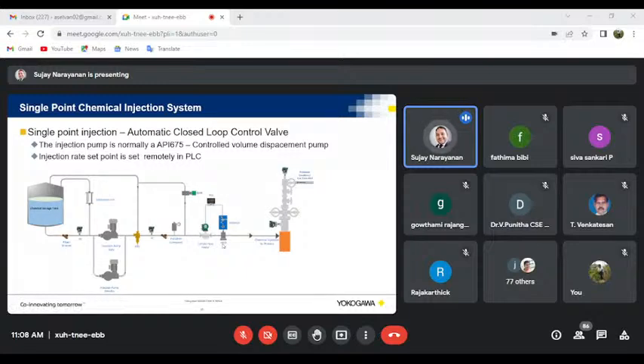It is called the injection rate control device, because control valves are for bigger pipes. If you see these lines, these are all half-inch tubings, because the flow rate is very small over here. So for such a small flow rate, we use what is called an IRCD, and like any control valve, you need an actuator. Then you can achieve a closed loop control action. In this case, you need not try to control the flow rate by using the pump stroke. You can put the pump stroke at 100%.